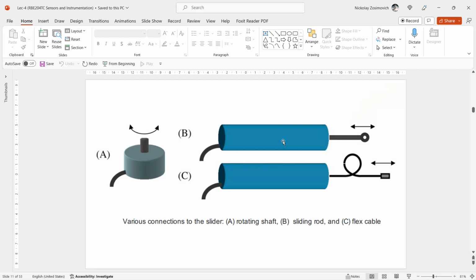In case of a liquid, one end of the flexible cable is connected to a float, and the other end is wound on a drum. When the level is rising or lowering, the drum winds or unwinds, and a rotational potentiometer measures the rotation of the drum. In case of a granular material, the measurement is usually performed intermittently. What does it mean? It means a weight on a flexible cable drops down until it reaches the top level of the material. The sudden change in the cable tension marks the distance over which the cable has been unrolled.